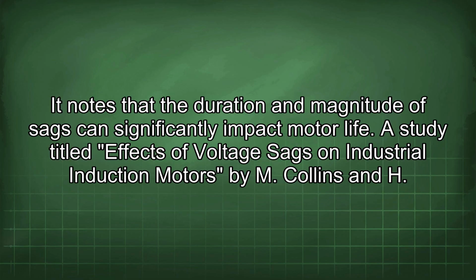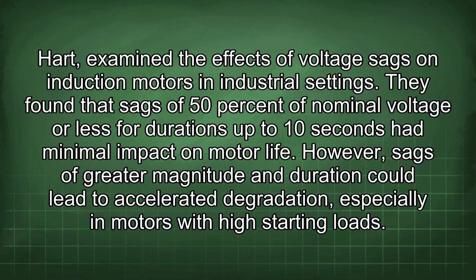A study titled Effects of Voltage Sags on Industrial Induction Motors by M. Collins and H. Hart examined the effects of voltage sags on induction motors in industrial settings. They found that sags of 50% of nominal voltage or less for durations up to 10 seconds had minimal impact on motor life. However, sags of greater magnitude and duration could lead to accelerated degradation, especially in motors with high starting loads.